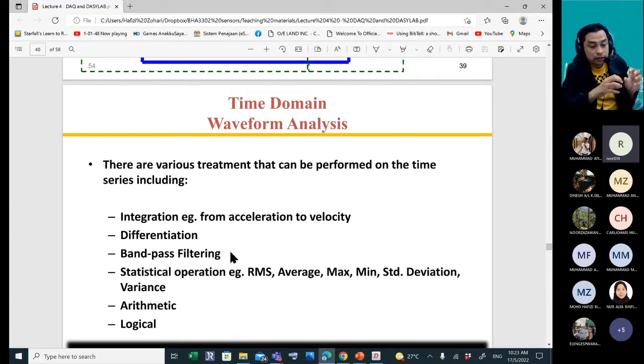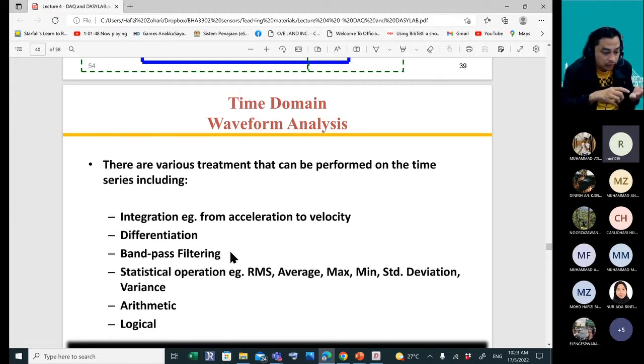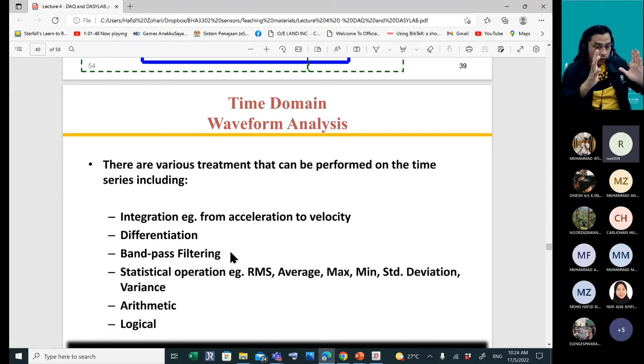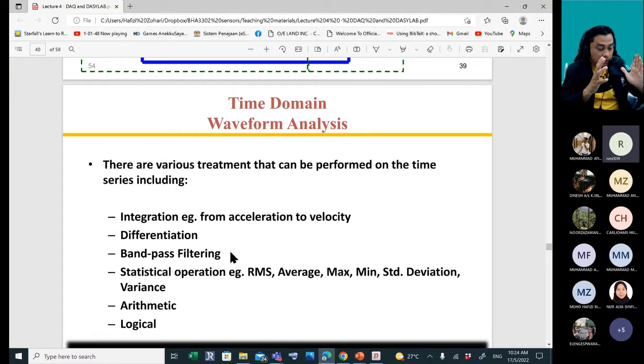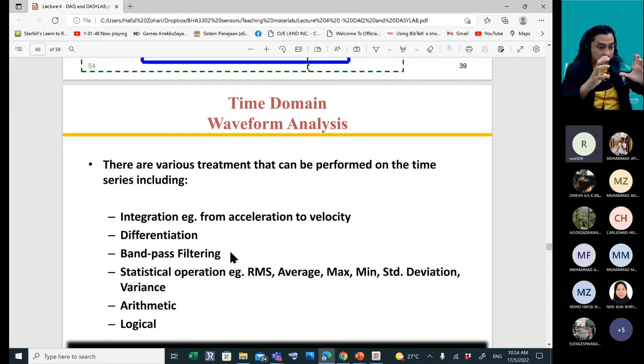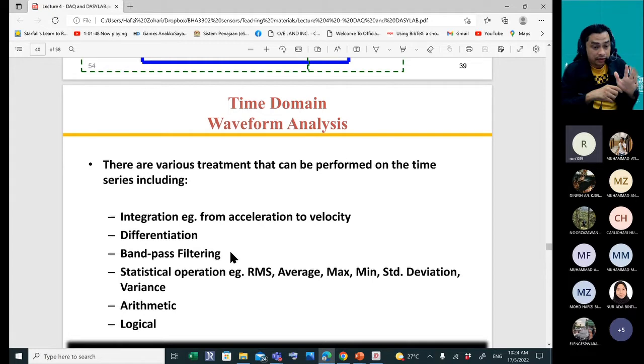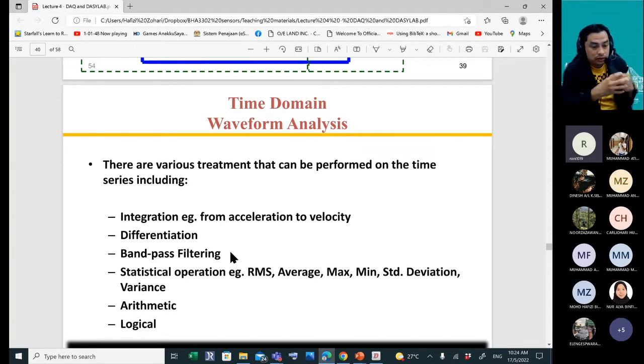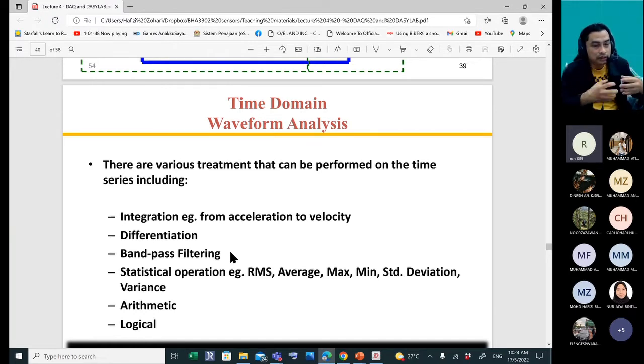The importance here: for one second of signal at 11,000 samples per second, you have 11,000 data points. You can compile all of this into just six values — RMS, average, max, min, standard deviation, and variance. So instead of 11,000 data points you only have six data points per second. This is why statistical information is very important when you create post-processed data.